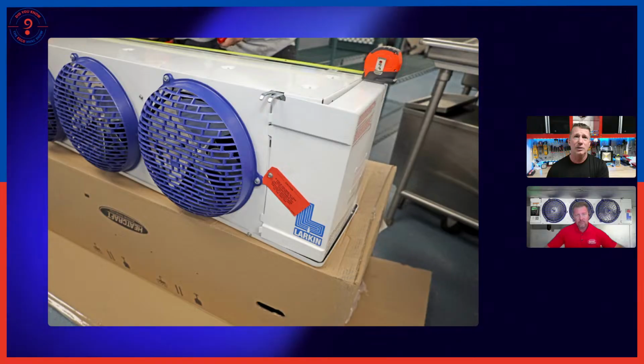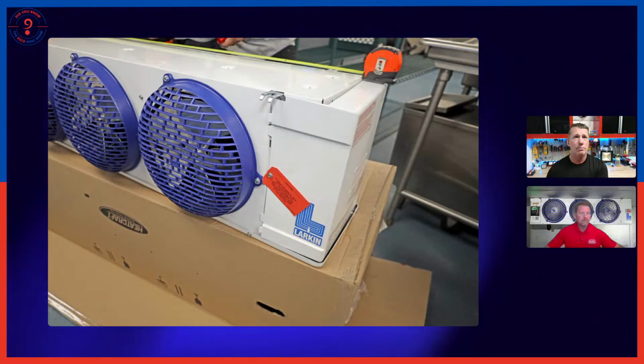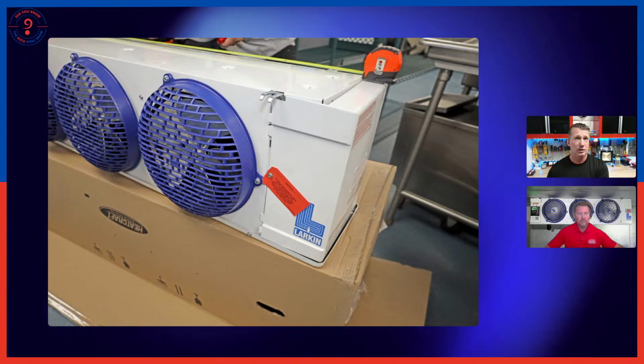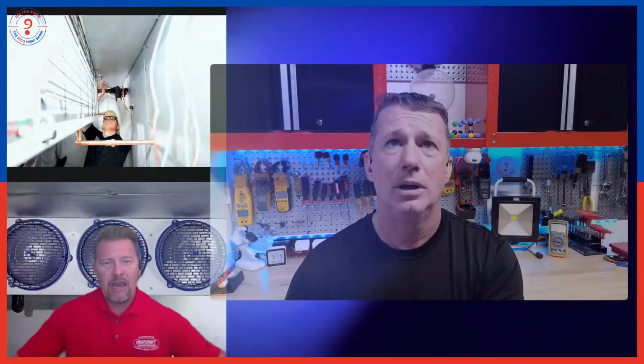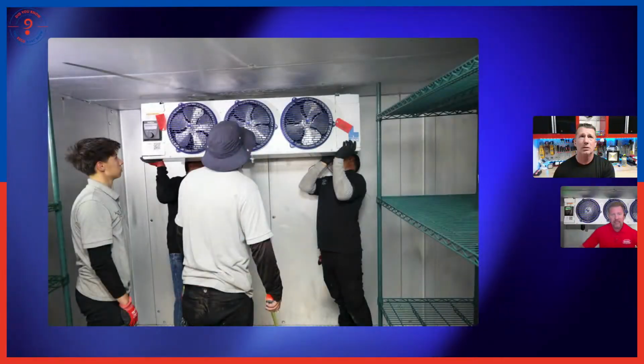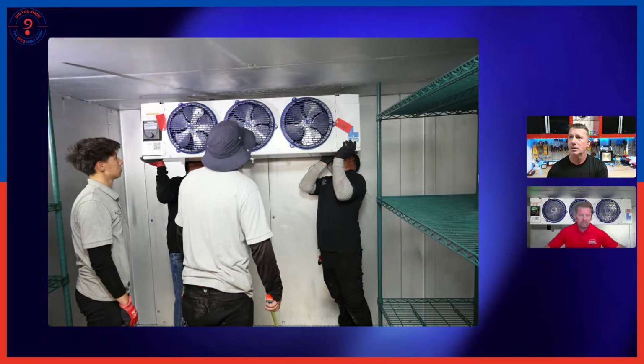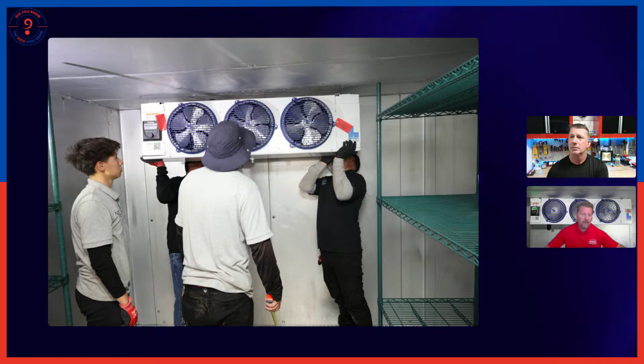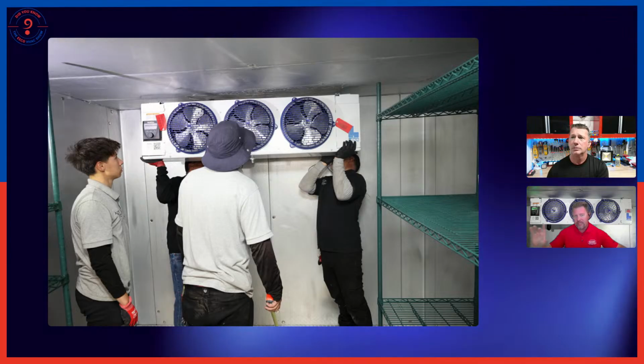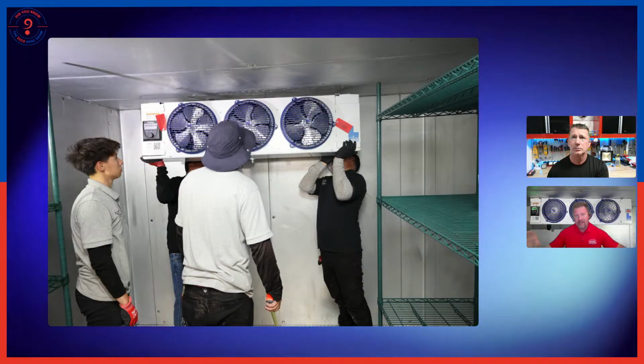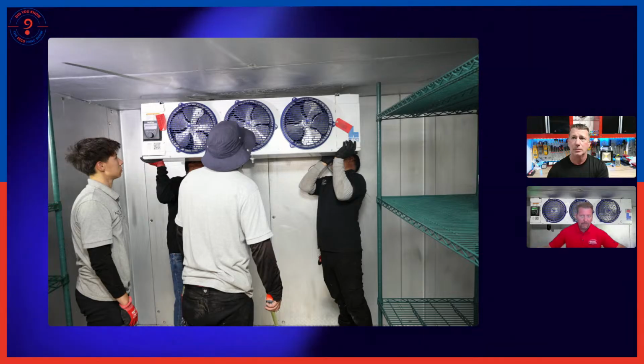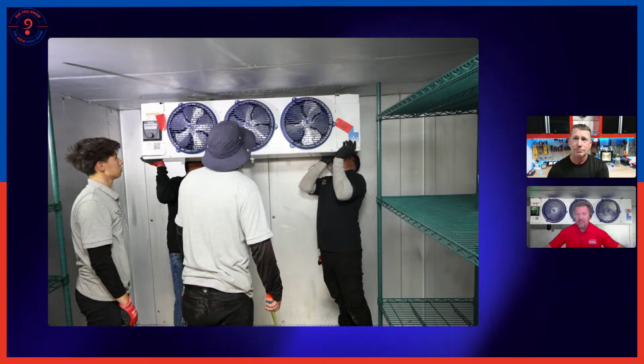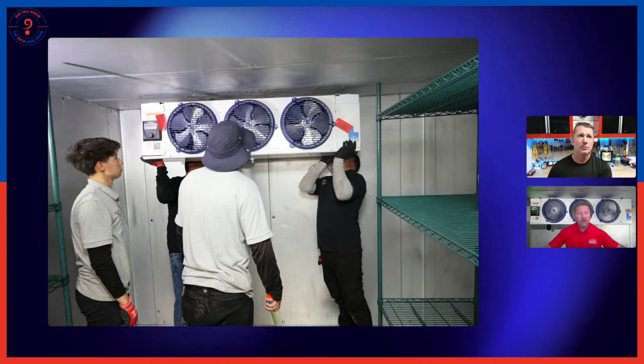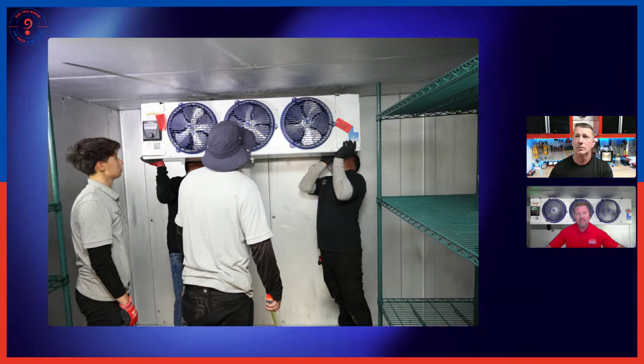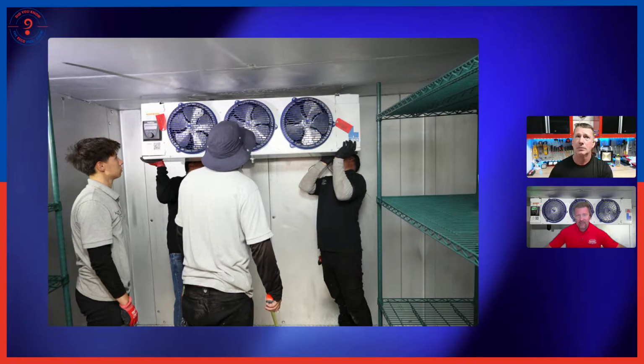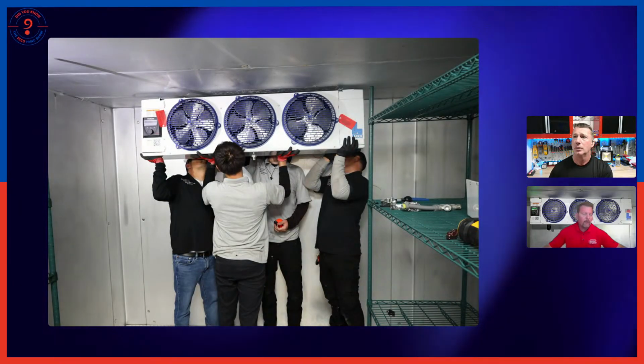So, one of the first things that I noticed looking at our unit is no major differences. It looks like an evaporator coil. And to the untrained eye, that's all it is. The untrained eye will not notice any differences. There are subtle differences. Our connection points on the back of the coil are protected now. You're going to see a metal enclosure on those. That wasn't something that was required with A1s. With A2Ls it is there. The other thing that stuck out like a sore thumb to me was that now there is a grate across the back of the evaporator that protects the coil.